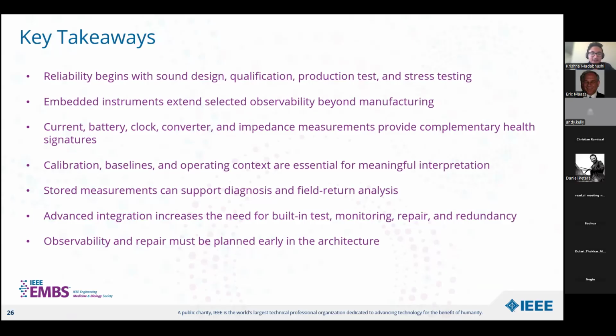We looked at several examples like current, battery, clock, data converters, and lead impedance monitoring. Each measurement provides only part of the picture. Its value increases when it's calibrated, repeated under known conditions, and compared with the baselines we established. Then the stored signature and trends can also preserve evidence for diagnosis in field analysis. They may not reveal the root cause directly, but they will show what changed and help us narrow the investigation.